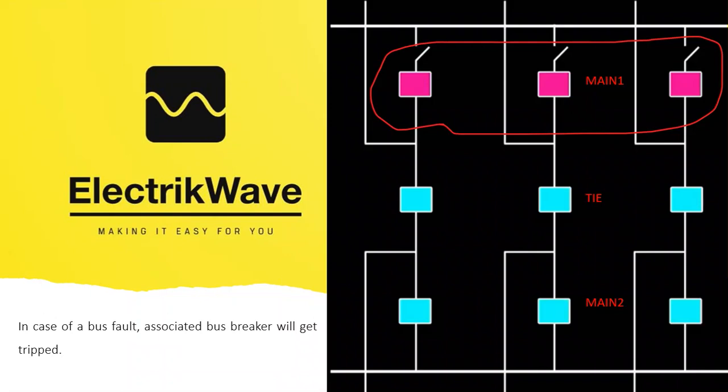During normal conditions, all the 3 circuit breakers are closed and both circuits operate in parallel and power is fed to feeders from the 2 bus bars. If the fault occurs on one bus bar, then with the help of the second bus bar feeder circuit breaker and tie breaker power are fed to feeders. This means each feeder breaker has to be rated to feed both feeders which are coupled by tie breaker.